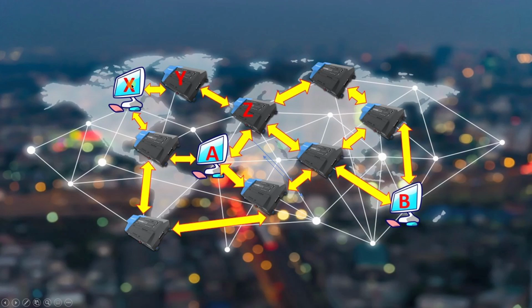For example, if a station is created in a supervisor or workbench with the X passphrase and you want to copy that station to a JACE with the Y passphrase, in the station copier you will have to use the X passphrase with which the station was created.